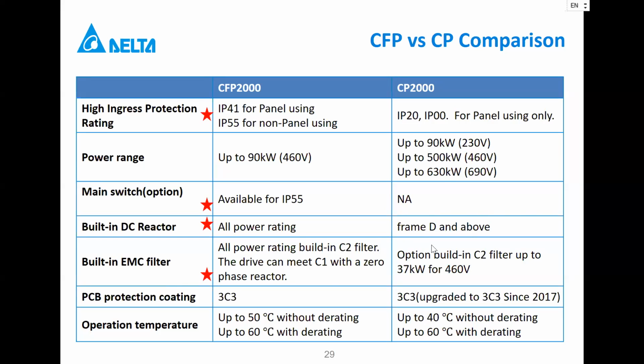Okay, please take note. Another one is the built-in EMC filter. For CFP 2000, all power ratings have a built-in C2 filter, and the drive can meet C1 rating with a zero phase reactor. But for CP 2000, there is an optional built-in C2 filter up to 37 kilowatts for 460 volts. So please take note of this.